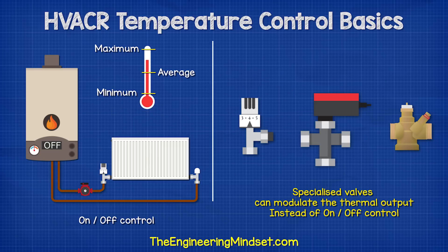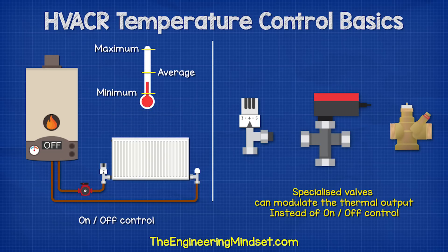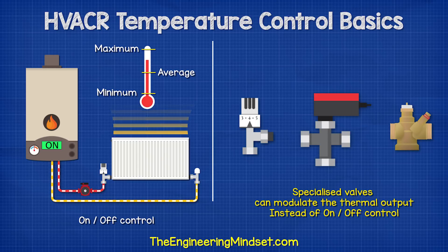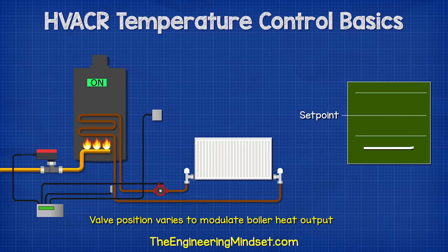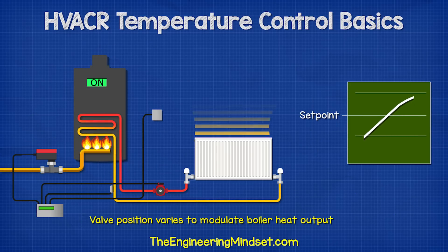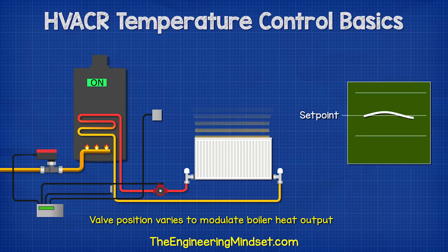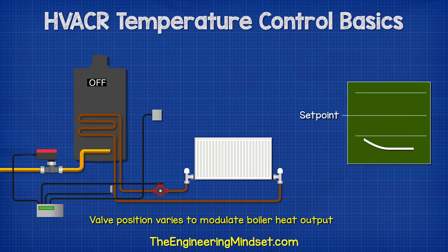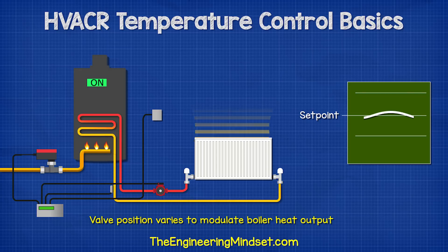On and off control makes it difficult to maintain a desired temperature. Instead, we can use special valves to modulate the thermal output, keeping the temperature within a certain deadband. In a simple heating system, when the gas boiler turns on, it will run at full power to heat the water, but then it reduces the gas supply by using a motorised valve. This reduces the heat output of the boiler rather than turning it off. The water temperature set point is kept in the deadband, so the heat output is equal to the heat leaking out of the room.